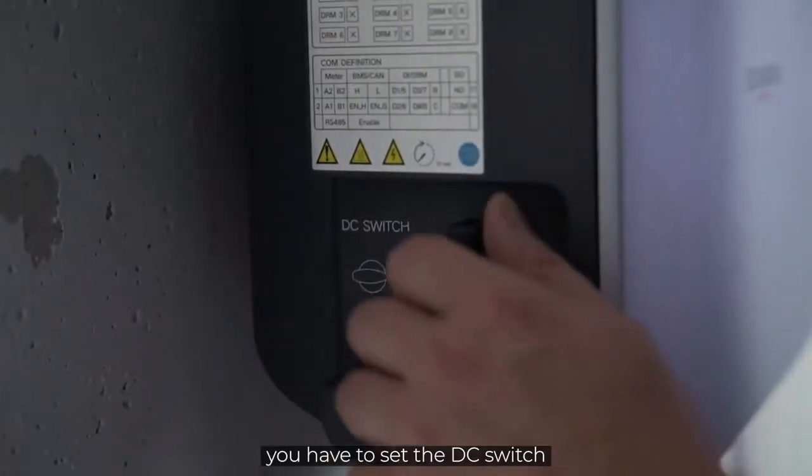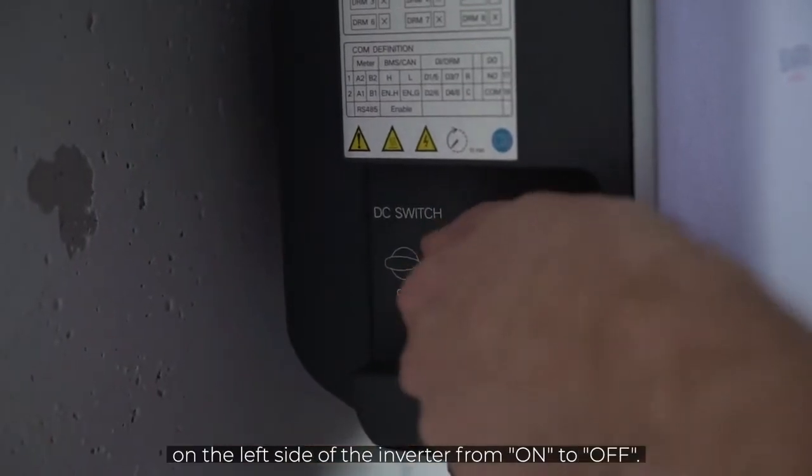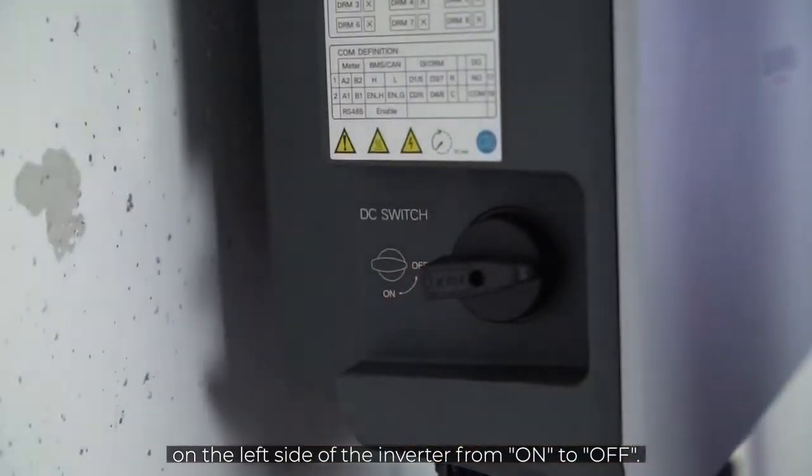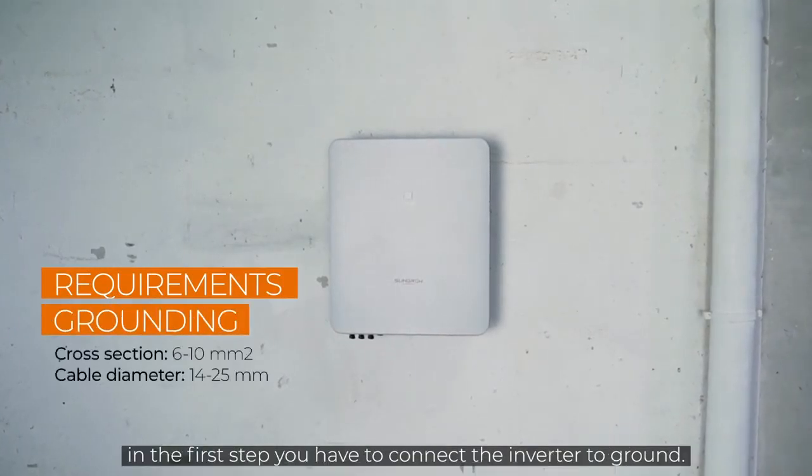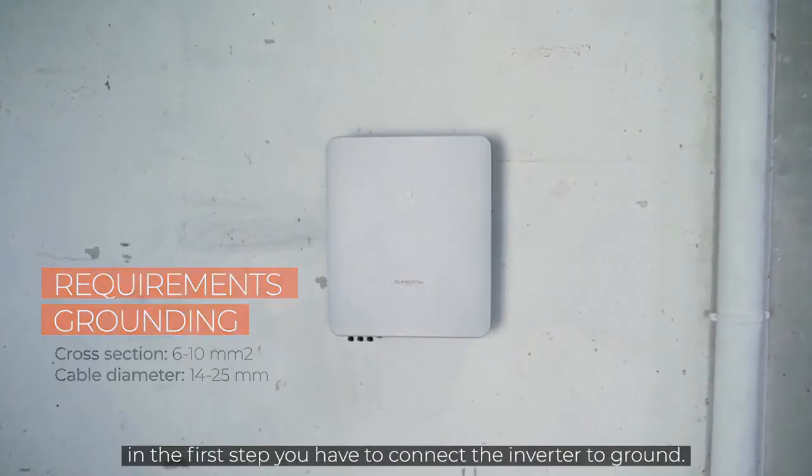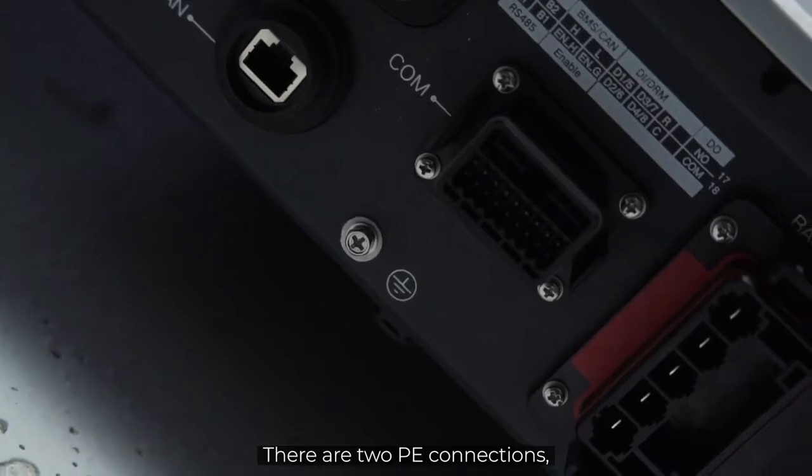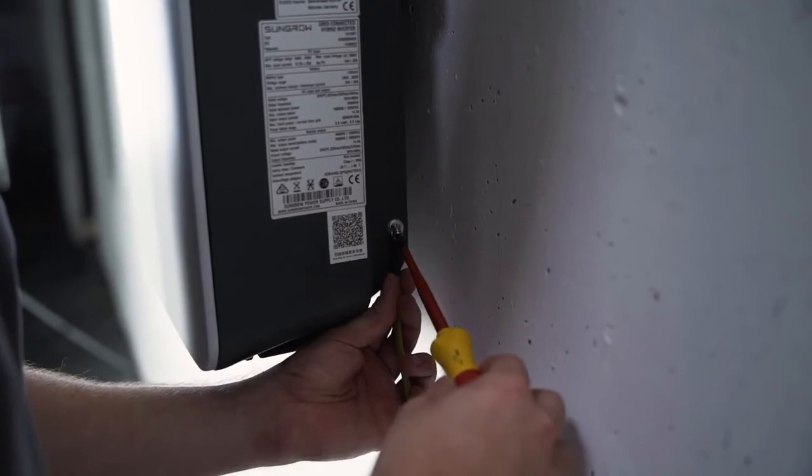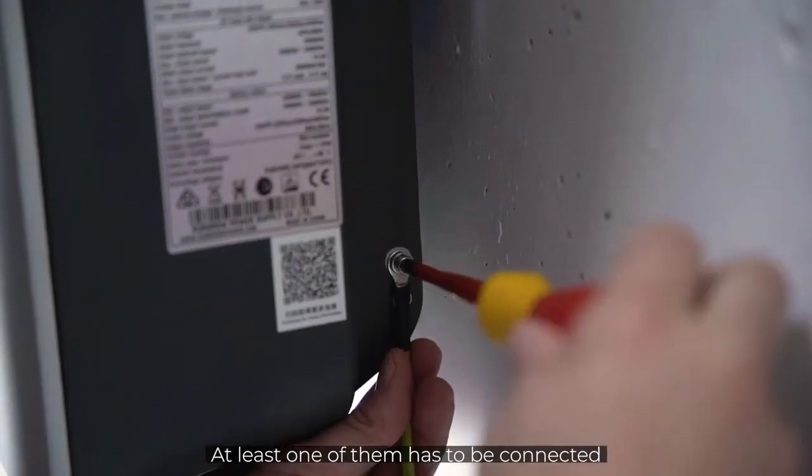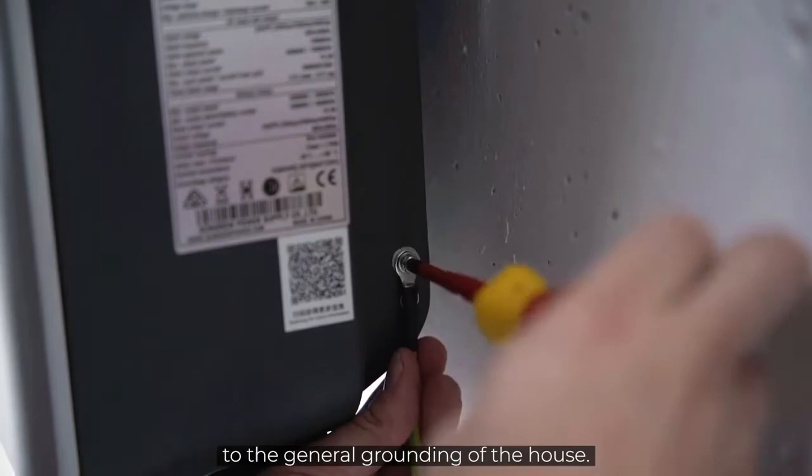Furthermore, you have to set the DC switch on the left side of the inverter from ON to OFF. Now, let's continue with the installation. In the first step, you have to connect the inverter to ground. There are two PE connections, one at the bottom and one on the right side of the inverter. At least one of them has to be connected to the general grounding of the house.